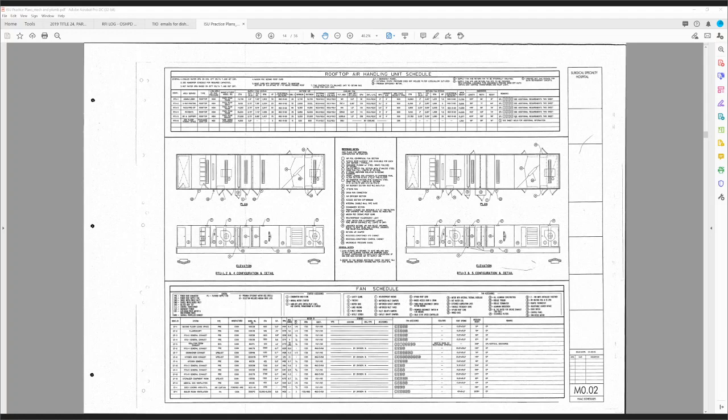Yeah, thank you. Bradley's perspective was actually very good too, because I did answer it right, but when I was reviewing it, there's also an additional light circuit to the unit, a little 120 volt circuit. So I did not assume there was some sort of control transformer in place. I looked at what made the most sense from an answer perspective on what's left, but it was not an obvious decision. I just wanted to put that out there.